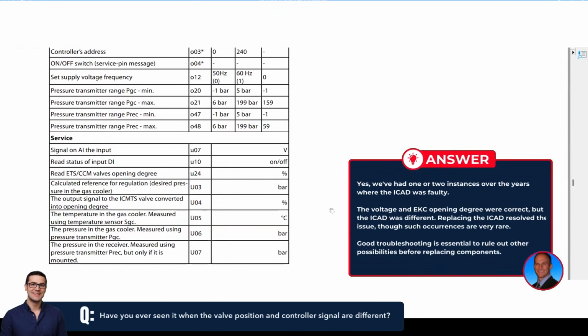We've had one or two instances over the years, I think, and it ended up being that the ICAD was bad from what I recall. Okay. So the voltage seemed okay. The opening degree in the EKC was at a reasonable level based on what the set point was and the pressure was of where we thought the percentage should be. The ICAD was different. And I think we ended up replacing the ICAD once or twice, and that resolved that. Yeah, and that's rare occurrences. Yeah, exactly. Once or twice over the course of however many years that thing's been on the market, which has been a long time. So not saying it can't happen, but it's very unlikely.